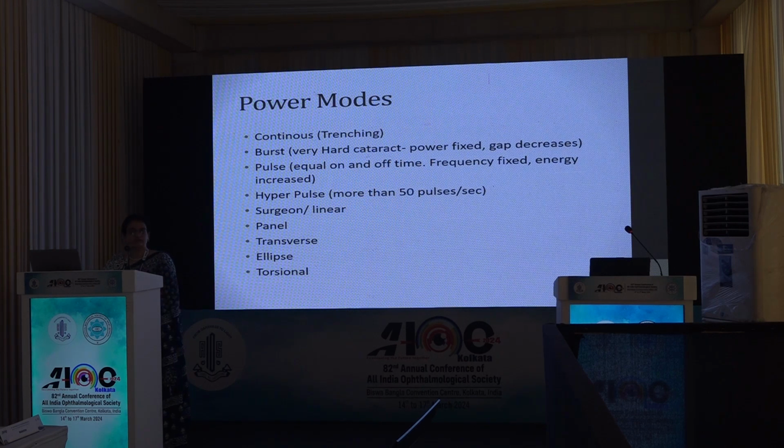Hyper pulse, more than 50 pulses per second. Surgeon or linear mode, as we press the pedal, the power increases. There is a panel mode, transverse mode, ellipse mode. In newer machines there is also a torsional mode. So with longitudinal there is a transverse side to side angular action.